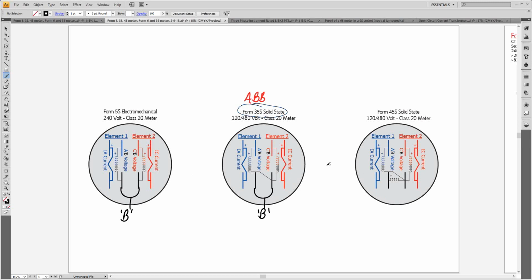When we get to the 45S, this was a GE meter that was an equivalent of the electromechanical 5S. When you would take the 5S out of a socket and replace it with a 45S, same idea, the jumper was still in place, with B phase connected between these two points. Now I've got three potential coils in my meter. I have a potential coil connected from the blue terminal, the center left on top, down to the common point where all the potential coils in this meter are connected.